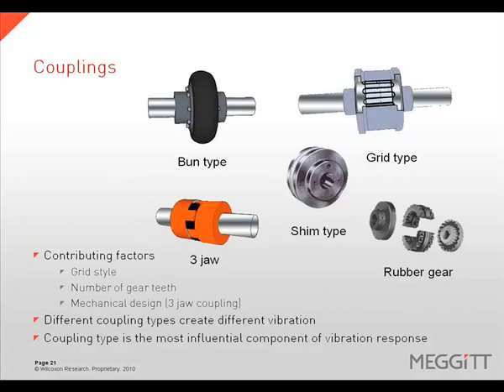Coupling type can be a major contributing factor to the vibration response of misalignment, as different coupling types will create different vibration responses. A band style coupling may exhibit the traditional 1x or 2x vibration response. However, with a 3-jaw coupling, the 3x vibration is the best indicator of alignment condition. Grid style or gear couplings will vary depending on how many grid elements or gear teeth are in the load zone.